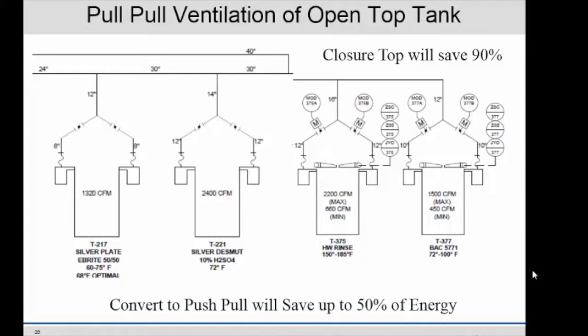Also, these tanks are pull. They're pulling on each side for ventilation. If you did push-pull, where you push the air across the top and pull, you cut the energy in half. The ventilation air is cut in half. Okay? You don't have to have as much air because you're not pulling from both sides. You're pulling from one side, and you only have to do half. It's a more efficient way of ventilating an open tank.